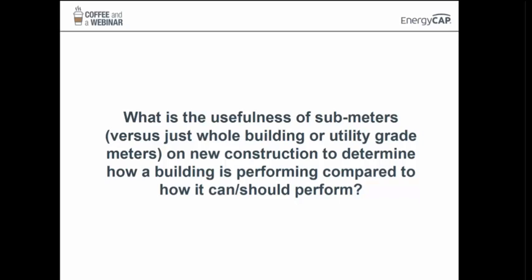I want to clarify that those charts that I showed were not technically meters. They were just trend information about the building automation system points. Well, you can see them as meters if you want to think about it in that manner. The reason we have all of those points is because they would exist on any campus that has electronic DDC control centralized, which most campuses do anyway. So we didn't really expend any extra dollars on making sure that all those points existed. They just existed for the fact that we wanted to control that space remotely anyway.